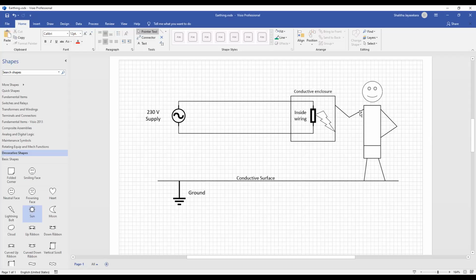So there should be a complete circuit for current to flow. So this is a 230 volt supply. For this person to get a shock, there should be a connection from the neutral or ground of this supply to earth. Now this circuit is complete. So if this appliance is faulty, your current will pass through this line, and it will touch the enclosure through the fault, and now this is the path. Then it will pass through the conductive enclosure, through this person's body, through the legs, and into the conductive surface. Make sure you know this: I have indicated this surface is conductive. Through the conductive surface this circuit will complete, right? So now there's a current flow through this person's body, therefore this person will get a shock.